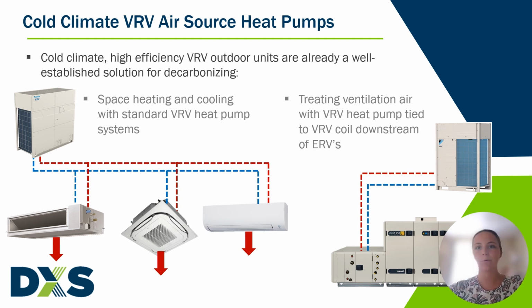And it's really important to understand the extreme cold climate capabilities of the systems, which are still able to extract heat from the ambient air even at extremely low ambient temperatures, with some models being capable of providing 100% heating capacity down to 0 ambient, with operating ranges well into the negatives. And this is something that other air source heat pumps can't do, which is why it's such a big deal that we can now use these VRV heat pumps to efficiently decarbonize hot water heating for both domestic hot water and building hot water heating.